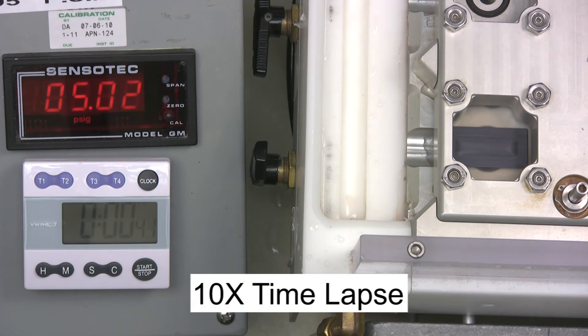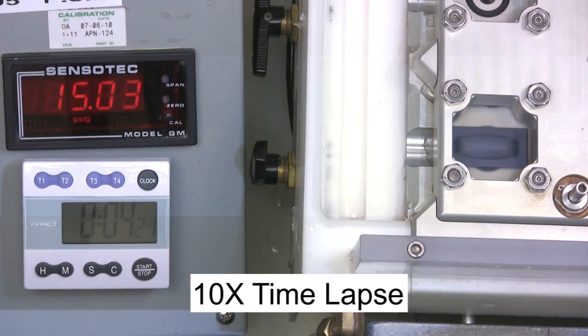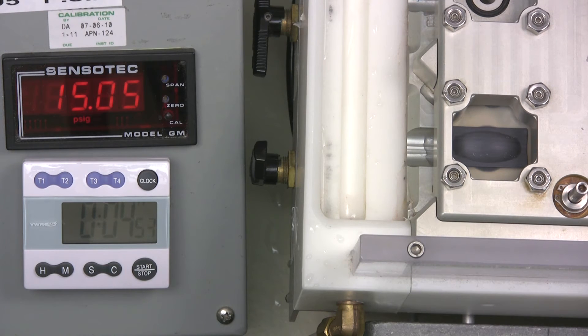Mounted to a polypropylene plate, this vent passes the 5 PSI test for one minute, so we'll now ramp the pressure to failure. Here we see some water droplets due to the membrane weep, and as we continue ramping the pressure up, the vent bursts.